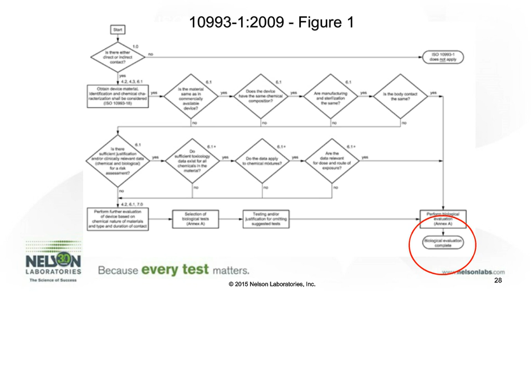Our first step for a medical device is material evaluation. And I know the engineers out there go through a lot of material decisions when they're making a device. But most of those decisions have to do with the functionality of the device, the cost of the material, or how easy it is to get that material. A lot of times they do not look at the biological impact of those materials. Really, you want to find a material that has the information you need to make a safe evaluation. It may save you a lot of money and time, specifically time, on the back end if you can make a wise choice on your materials when you're looking at biocompatibility.